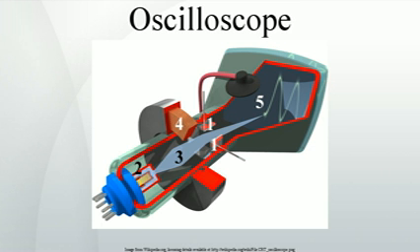Other instruments convert the results of their measurements to a repetitive electrical signal, and incorporate an oscilloscope as a display element. Such complex measurement systems include spectrum analyzers, transistor analyzers, and time domain reflectometers, TDRs. Unlike an oscilloscope, these instruments automatically generate stimulus or sweep a measurement parameter.